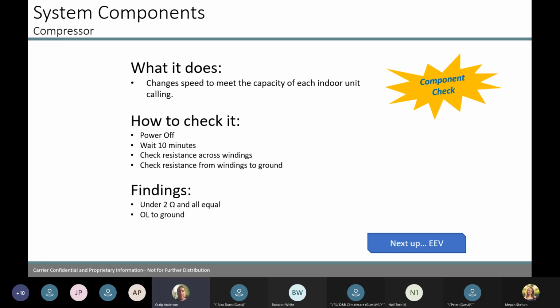So anytime you talk to a service guy on the phone or anything like that, you had a leak, I add a little bit of gas in it. No, take it out, make sure the leak is fixed, and weigh it in. If we weigh the gas in, we've taken that out of the equation. Doesn't matter if it's a standard air conditioner or a modulating air conditioner. Weigh your gas in. That is out of the equation when that is done. I know it's a pain, but it needs to be done, especially when we're dealing with a modulating compressor.